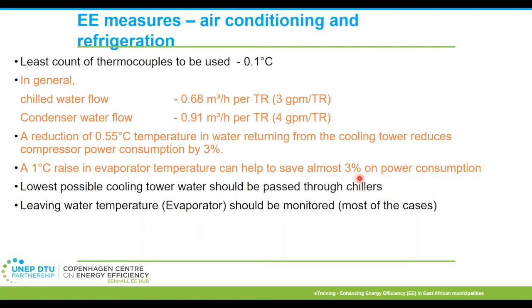This again is one of the case studies in one large commercial complex, wherein it is not limited to one specific measure, but there was a lot of optimization done, mostly with respect to the chilled water flow rates and the pressure variation, pressure optimization for the cooling water side, and airflow optimization. So all these types of measures were implemented, and then you can see what the power consumption was before, and after implementation what the power consumption is.